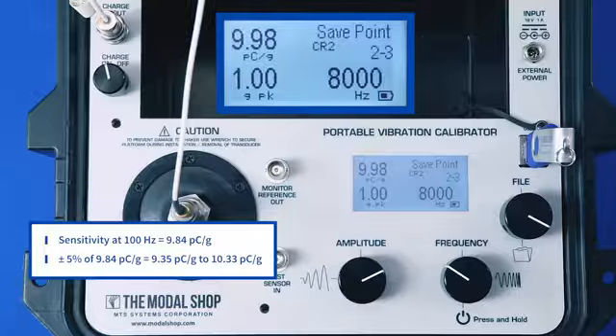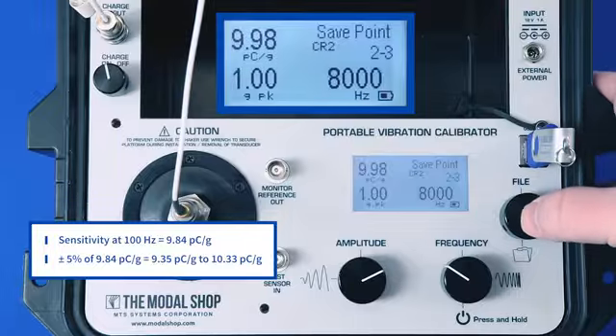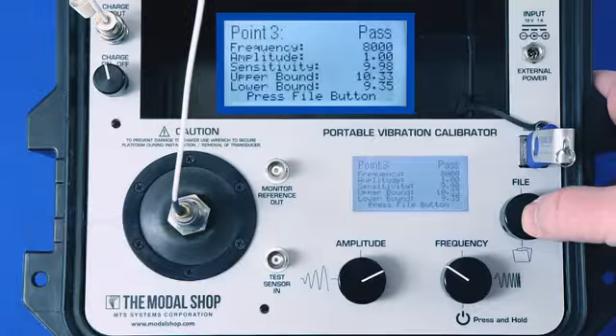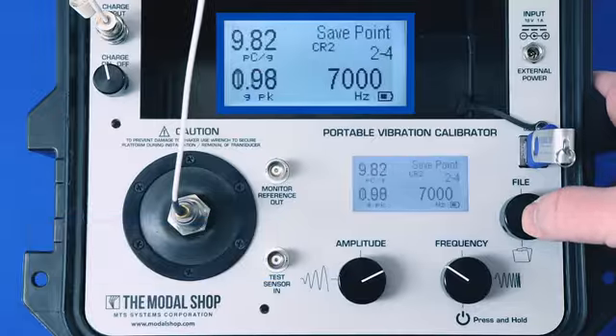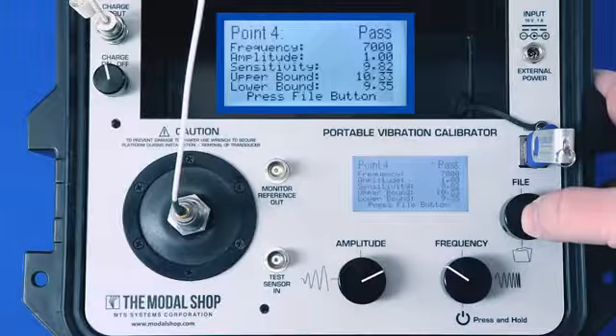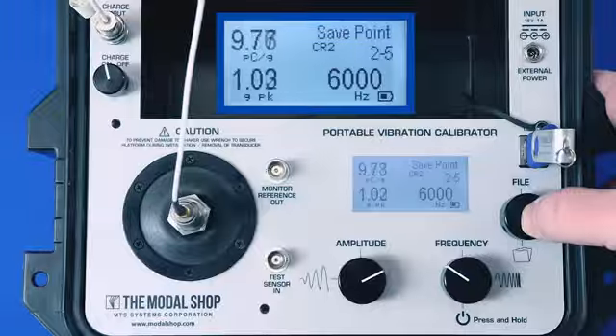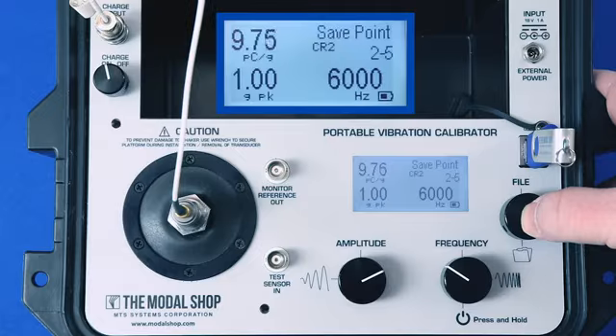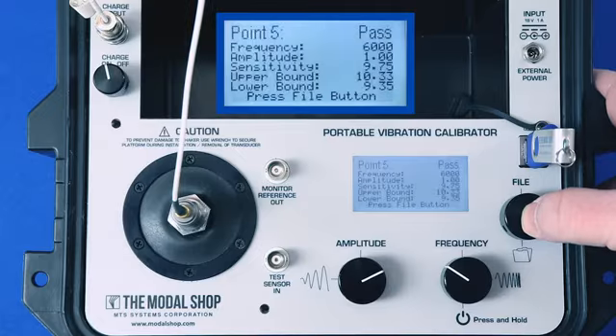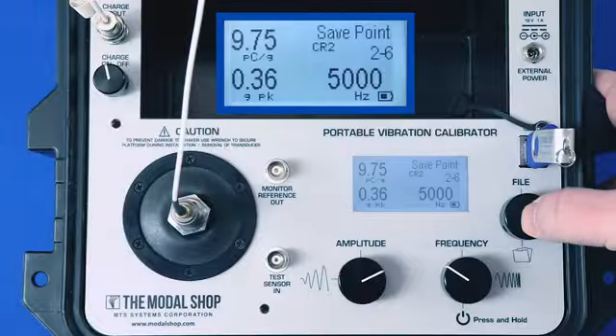And that's going to be the same for the rest of the test points for this accelerometer. At 8,000 Hertz we pass, and now I can go relatively quickly. I'm waiting for the amplitude to settle on 1 G peak, and then each time I'm just going to go ahead and hit the File button, and that saves the data point to the memory, gives me the pass-fail screen, and then one more click and I advance to the next test point.